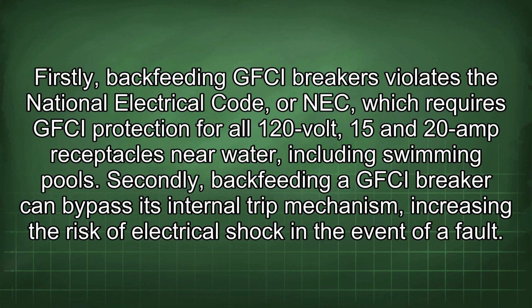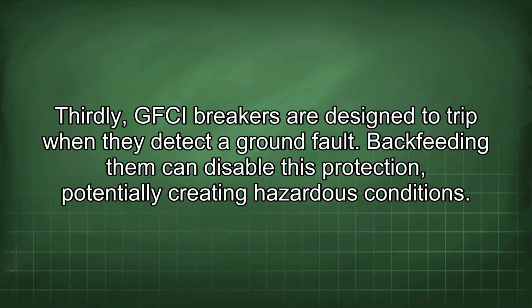Secondly, backfeeding a GFCI breaker can bypass its internal trip mechanism, increasing the risk of electrical shock in the event of a fault. Thirdly, GFCI breakers are designed to trip when they detect a ground fault. Backfeeding them can disable this protection, potentially creating hazardous conditions.